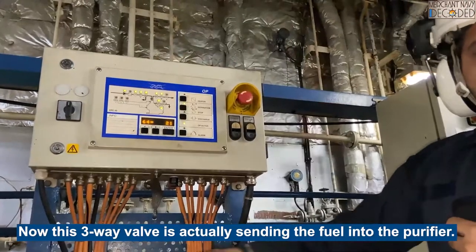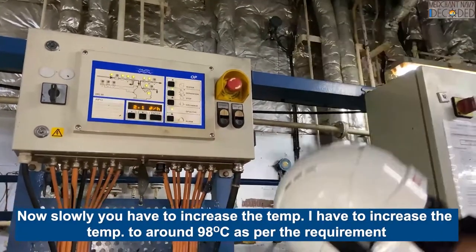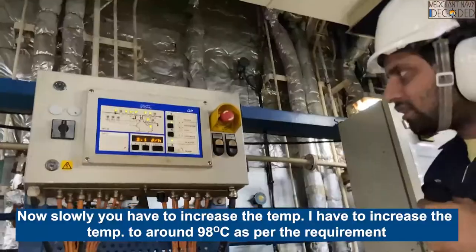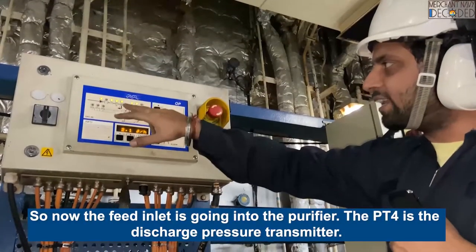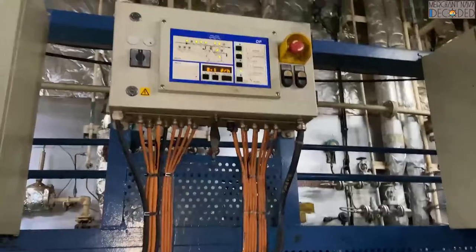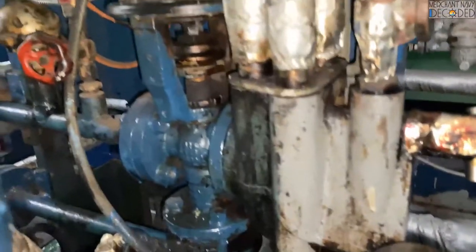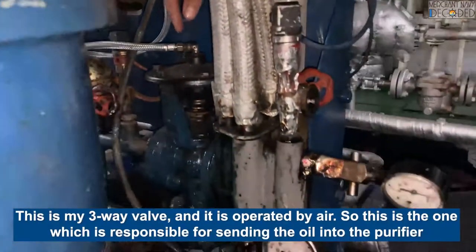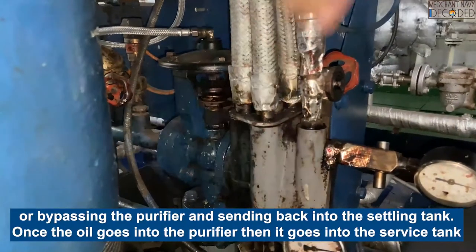Now I have to increase the temperature slowly, to around 98 degrees as per the requirement. The feed inlet is now going into the purifier - this temperature transmitter starts monitoring it. This is my 3-way valve, operated from here. This is the one responsible for sending the oil either into the purifier or bypassing the purifier and sending it back into the settling tank. Once the oil goes into the purifier, it goes into the service tank.